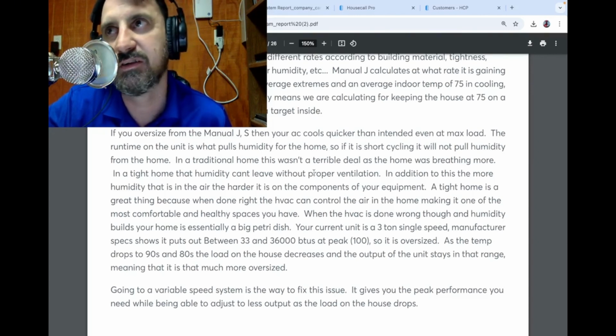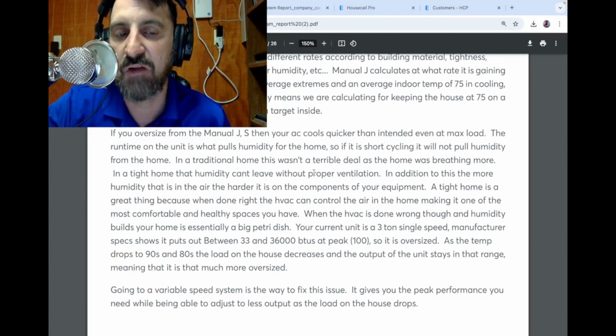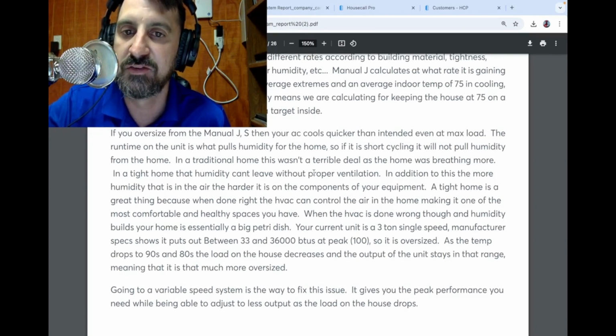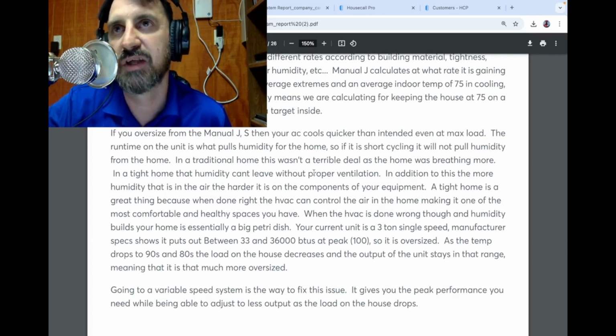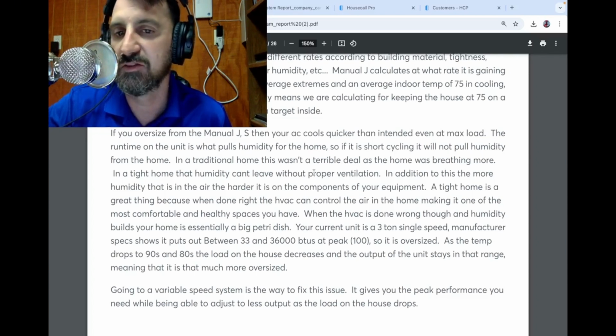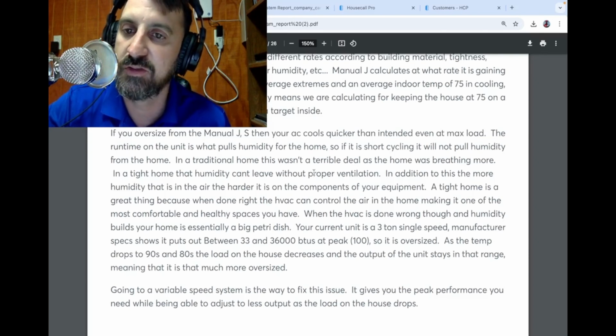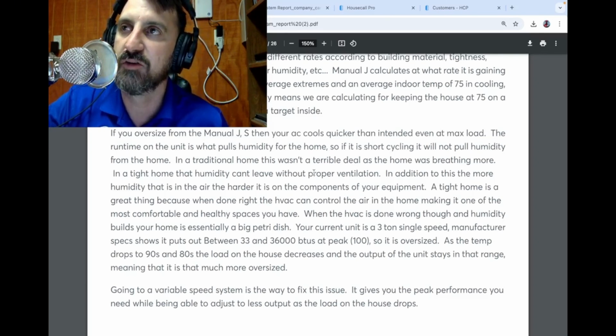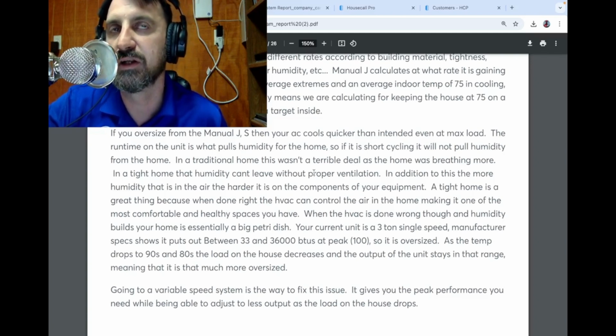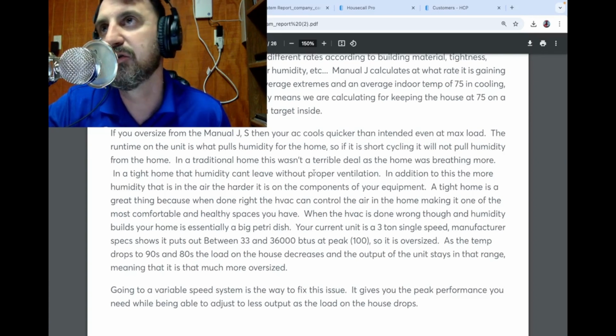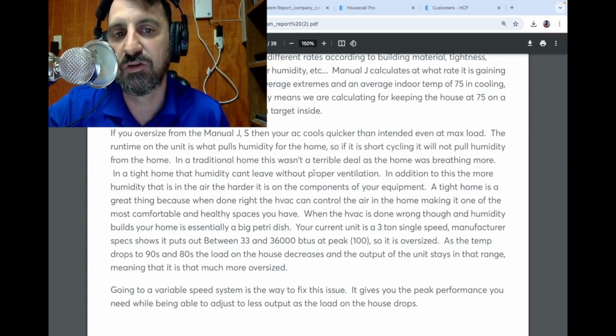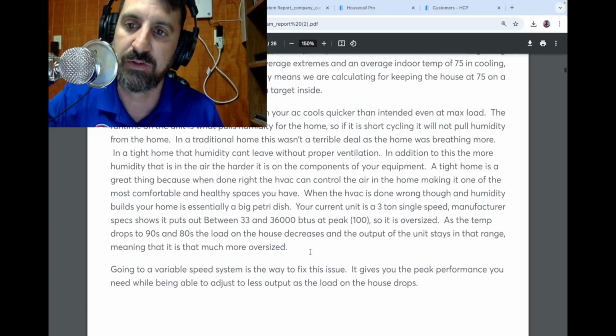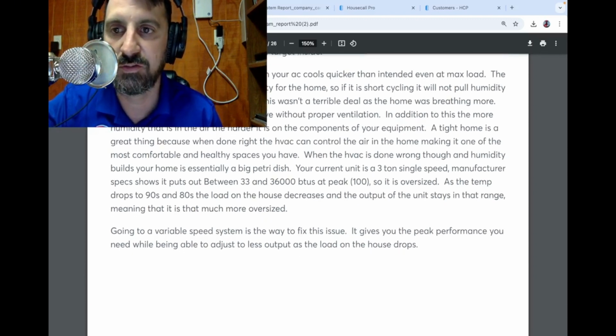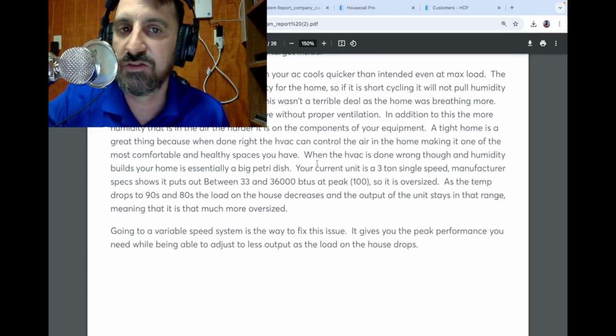If you're like, well, I'd like to keep my house at 70, you really need to be on the variable speed and allow that variable speed to do its thing, because if you set it at 77, 78 and it doesn't cycle as much as the report thinks that it's going to, then you're basically not going to cycle in the spring and fall when it thinks that you'll have at least some minimum runtime on the unit. You likely won't have any at all, which will allow humidity to build up. So basically, this goes through if you oversize the AC, your AC is going to short cycle.